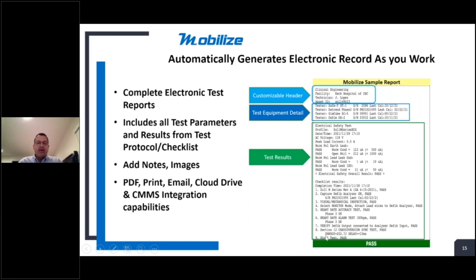As you can see down here, number 8, we have the energy that was captured for the defibrillation and the delay during that cardioversion test that we did. And so all of the test results would be on this report, and you would have a pass if everything passed, or a fail if any one test failed. So it just gives you a nice, complete report without having to manually do any extra work to obtain it.